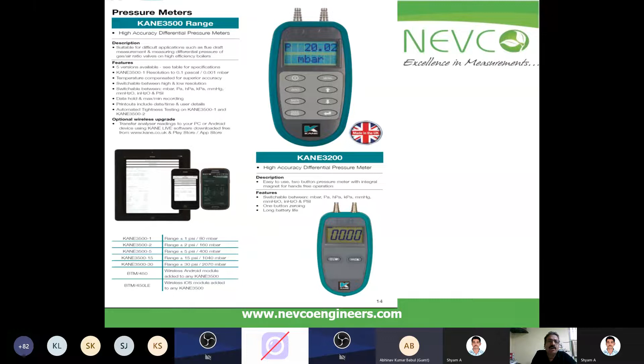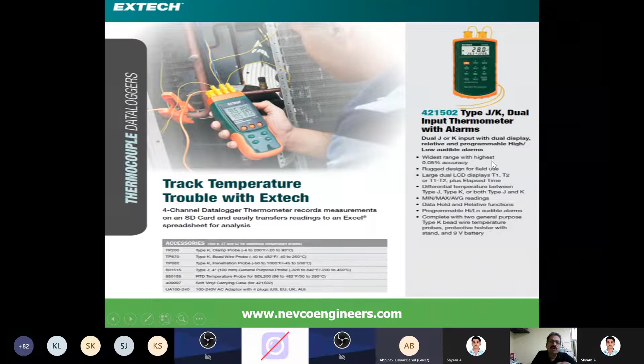Then we have temperature thermometers, like digital temperature thermometers. Then we also have single K-type, J-type, single input thermometers, with more capabilities for better diagnostics. This is from Extech. And another, this is called dual input. There are two inputs, one for K-type or one for J-type, whatever thermocouple you use. We have two channel as well as 4 channel. Then we also have 3 channel. Then we also have 12 channel. So you have single channel, dual channel, 3 channel, 4 channel, 12 channel with data logging. With an SD card, you can download the data afterwards.